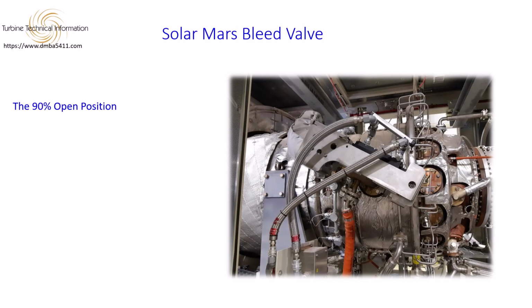The 90% open position. You may see the valve capable of going to 90% open. That is not a start condition, that is an overspeed protection response for the power turbine. Different scenario. Different logic. And on SoLoNOx machines, the bleed also plays a role in emissions control. So its position is not only about surge, it can be part of the combustion air management strategy.